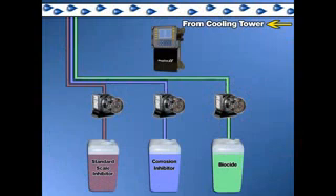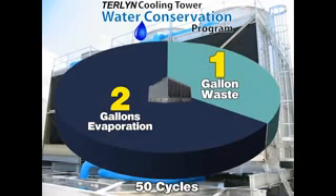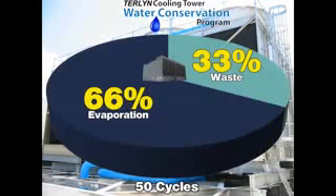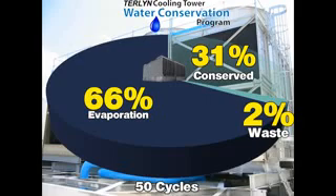The Terlyn program incorporates industry-standard corrosion inhibitors, biocides, and feed equipment. As a result, upgrading to this advanced water conservation technology is as easy as replacing one treatment with another. Utilizing the Terlyn program at 50 cycles of concentration requires only one gallon of wastewater for every 49 gallons of water evaporated. This reduces cooling tower wastewater discharge from 33% of the total water used to only 2% — a 31% reduction in the total water required by the cooling tower.